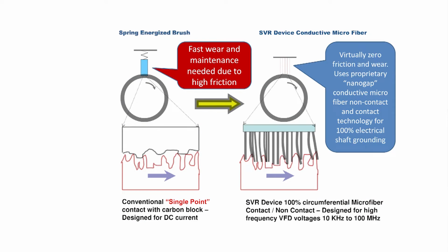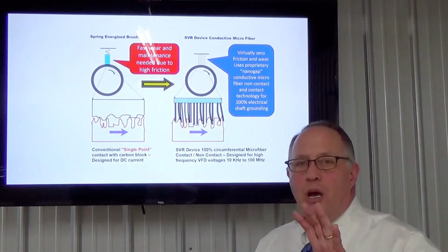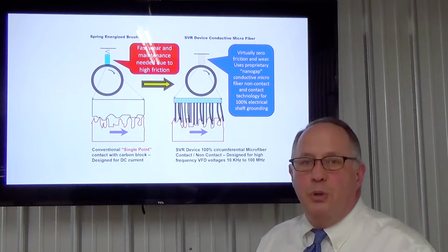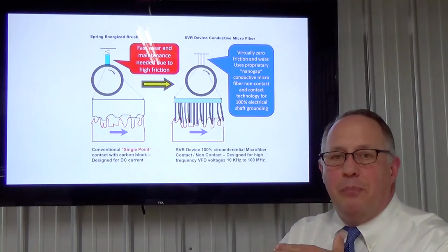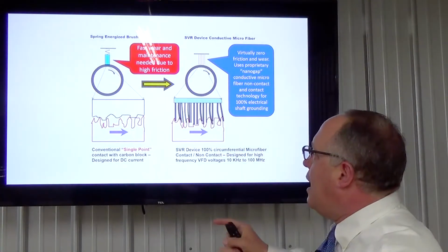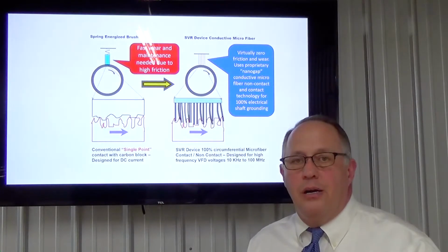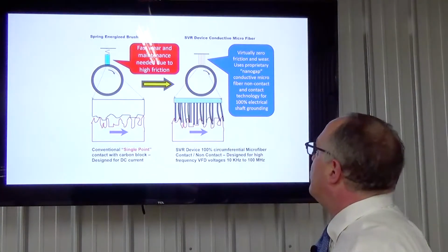Using the spring energized brush, like I had said, my first introduction to that, they can have fast wear, maintenance needs due to high friction. Conventional single point contact with a carbon block, I said graphite, carbon, graphite, but you can see the shaft on a blown up is not really as smooth, and neither is the pad itself. So over time, it can wear, and you have to stay on top of that maintenance-wise.